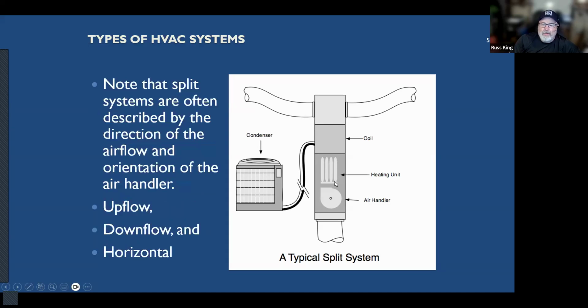Note that the air handler, we can describe that as an upflow, a downflow, or a horizontal, and that's based on the direction that the air is blowing. So you've heard the expression an upflow furnace or a downflow furnace or a horizontal furnace. That's just the direction that the air is blowing. This example here is an upflow air handler, or you can set it on its side and it can be a horizontal furnace, or you can flip it upside down and it can be a downflow furnace where the air blows down.